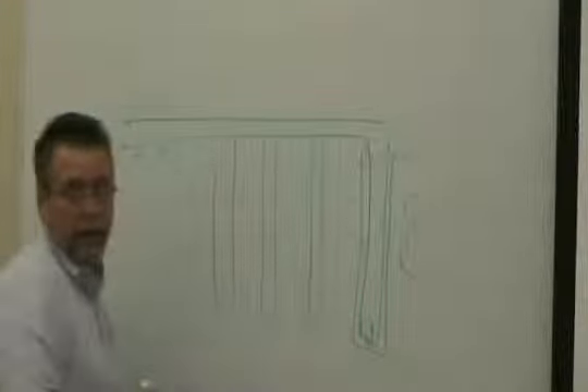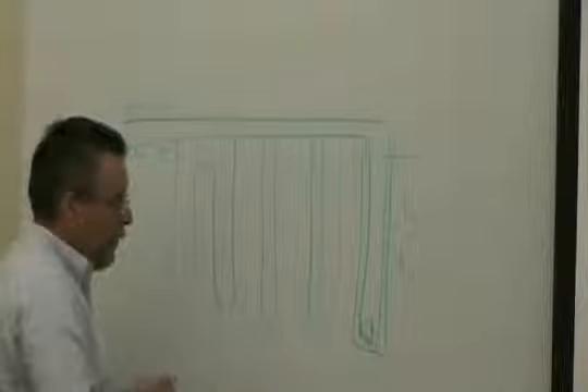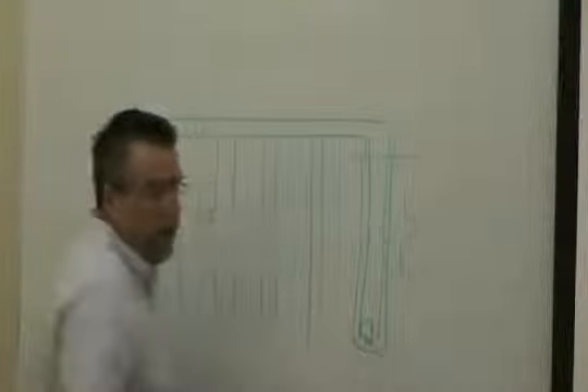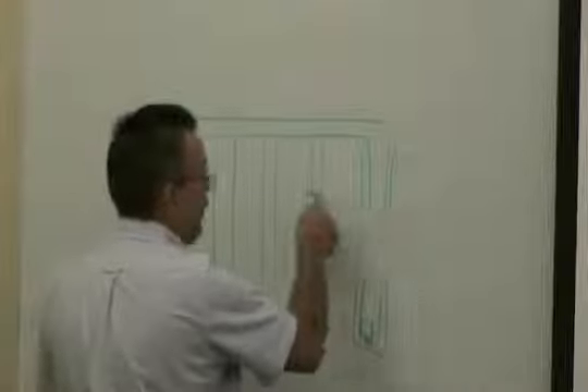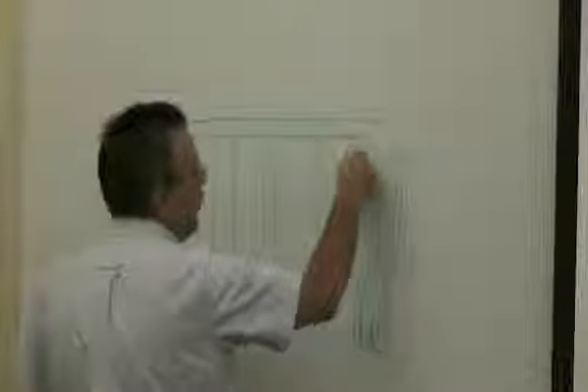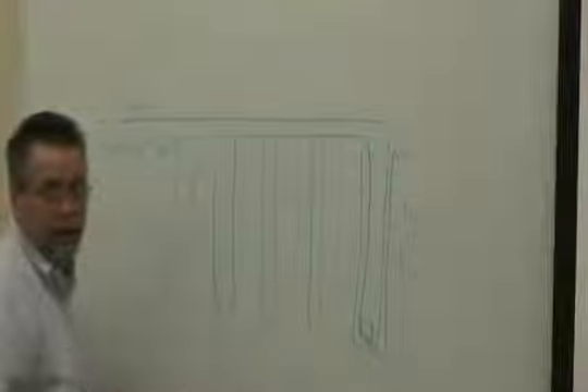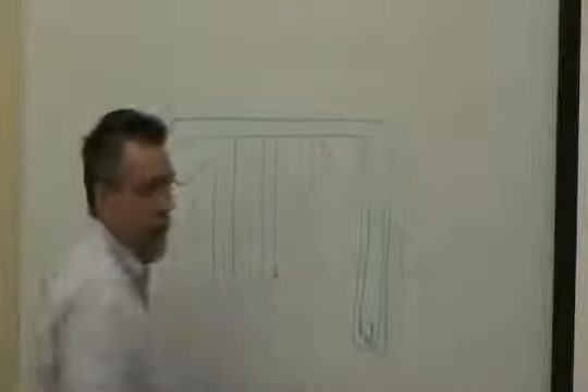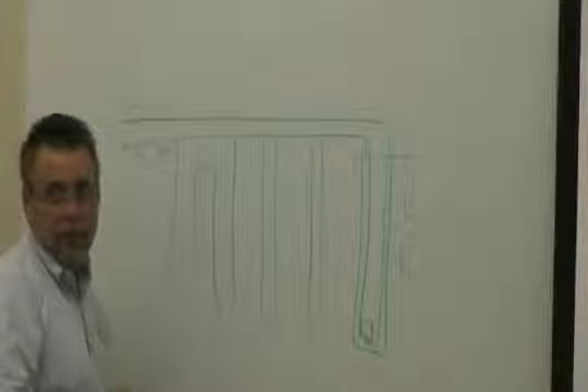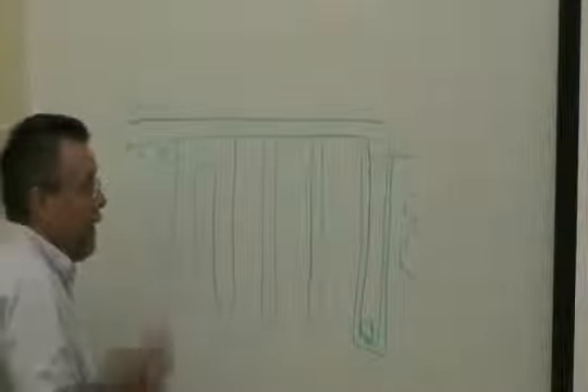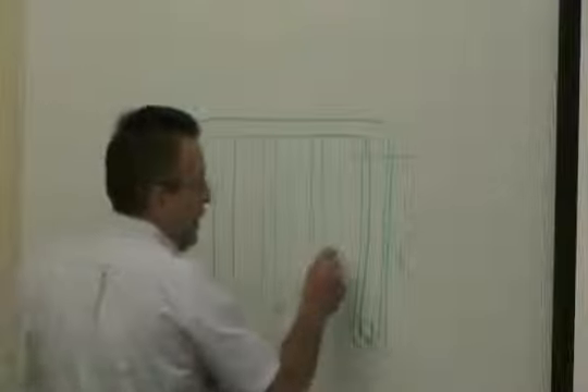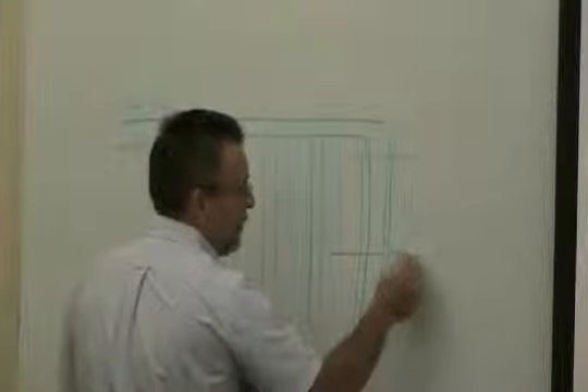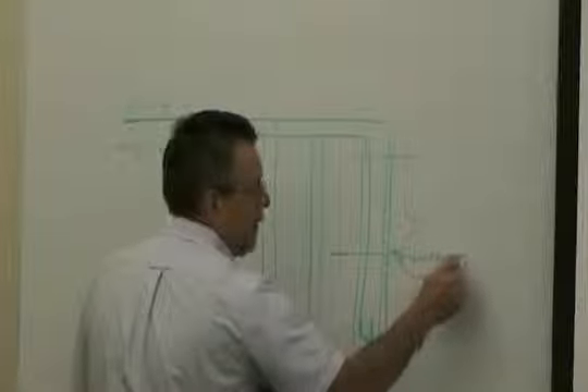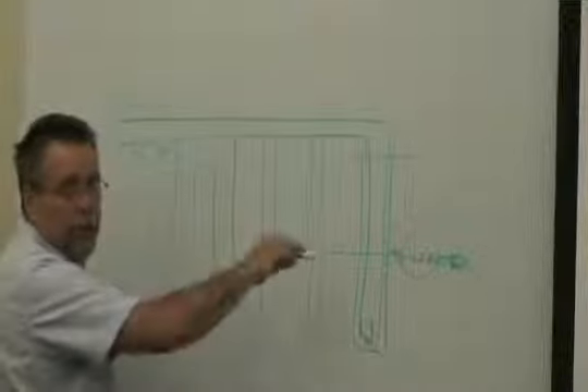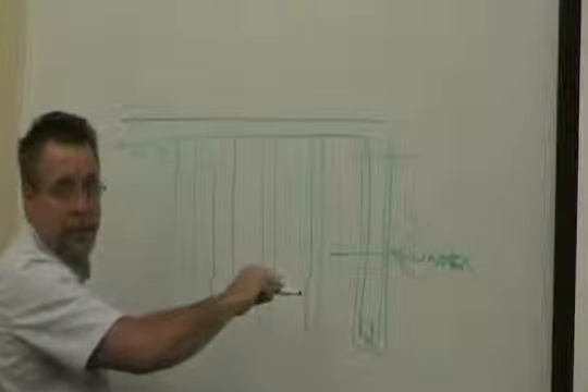Do they always hit water or do they just open it up? No, what you normally do in a test well, or if you're going to do a geothermal application, you come out and drill 1 or 2 wells. And they test the ground. They actually heat the water up, put it in the ground, and bring it back up to have a heat source. They're testing the conductivity of the ground to see what kind of heat rejection or heat absorption they can get out of the ground. The ideal ground is rocky with water flow through it.